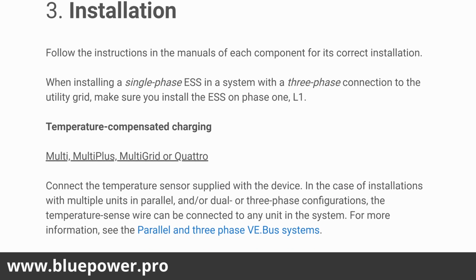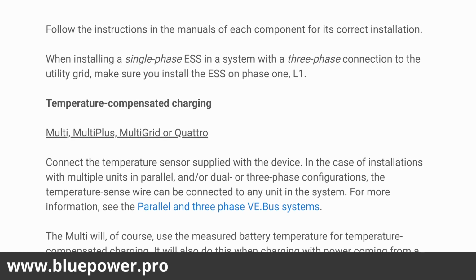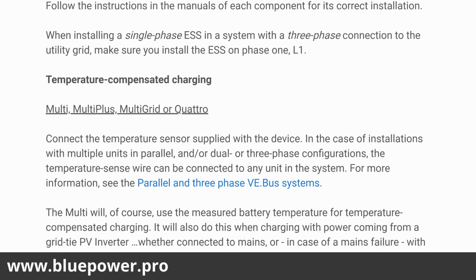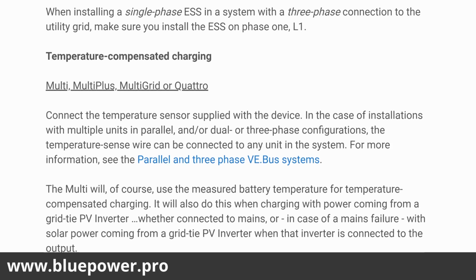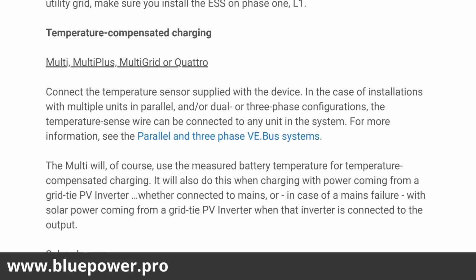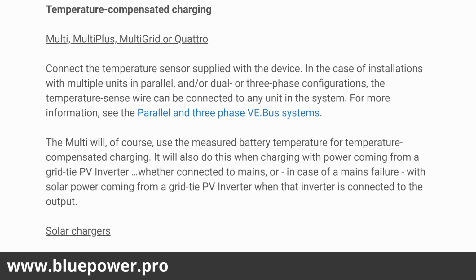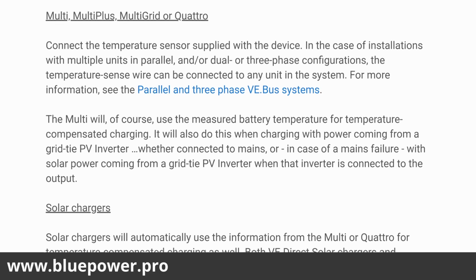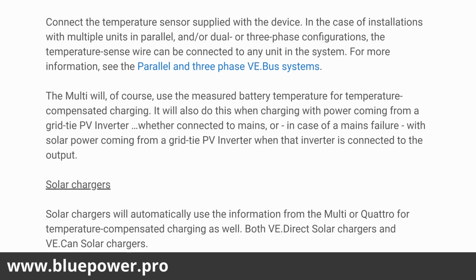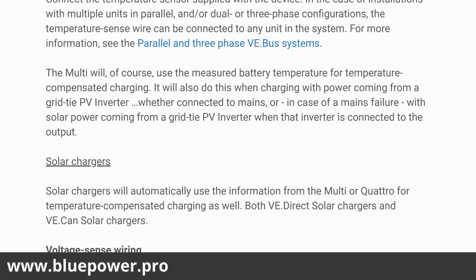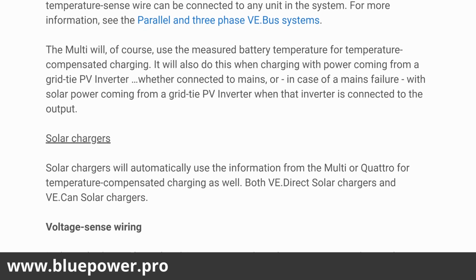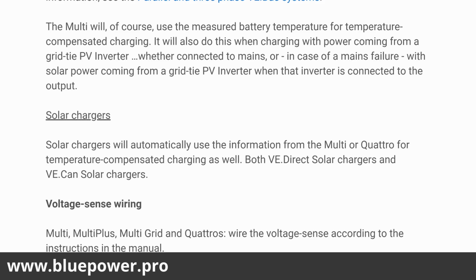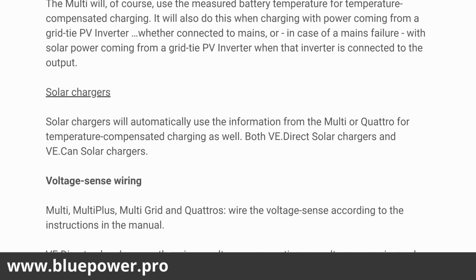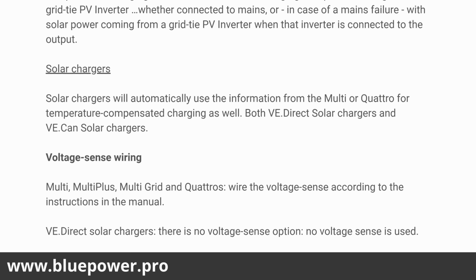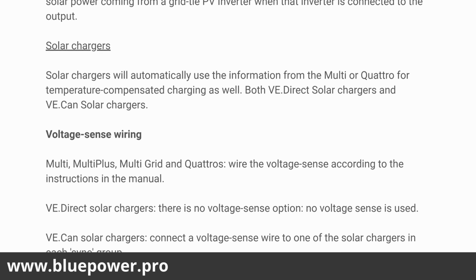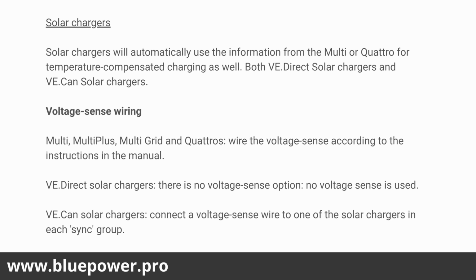So on the installation side, we've got temperature-compensated charging. That's on lead-acid batteries. You require temperature compensation if you're installing in extreme temperatures, cold or hot areas. Then you can connect the temperature sensor, which is supplied, onto the temperature sense terminals, which all of the Victron inverters have included. That temperature sensor can be connected, and you can then adapt the settings to apply the temperature compensation according to the measured temperature of the battery bank. That's not a requirement for lithium batteries, so you can use that temperature sensor and plug it into your Cerbo GX and rather measure your room temperature or something.